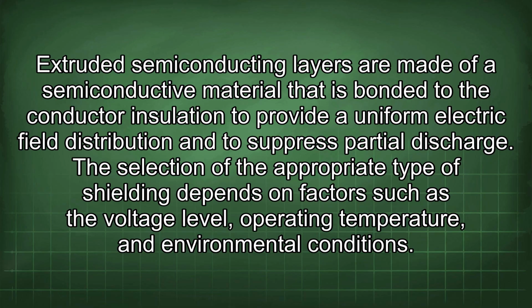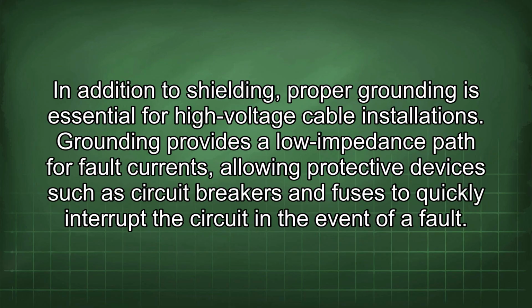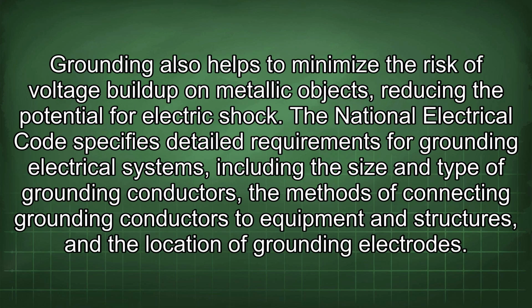The selection of the appropriate type of shielding depends on factors such as the voltage level, operating temperature, and environmental conditions. In addition to shielding, proper grounding is essential for high-voltage cable installations. Grounding provides a low impedance path for fault currents, allowing protective devices such as circuit breakers and fuses to quickly interrupt the circuit in the event of a fault. Grounding also helps to minimize the risk of voltage buildup on metallic objects, reducing the potential for electric shock.